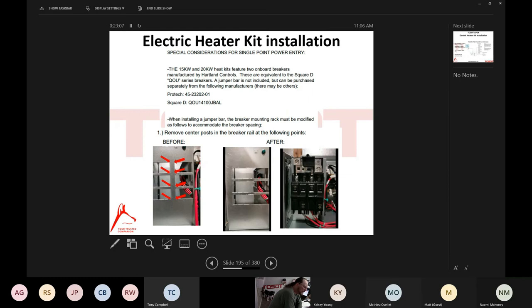Guys, this is something unique to Canada, so I'm told. If you're utilizing the 15 and the 20K electric strip, there's two breakers, right? But I'm told that the Canadian electrical code requires that there be a single connection point for that. You cannot bring it to two separate breakers for one appliance. It needs to have a single connection point, single point of power entry, as the header says there.